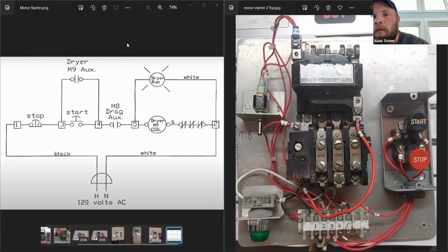I guess from there I'd go with your switch. If your switch isn't pulling in the coil... okay, now the coil is pulling in. The light's coming on as long as you hold the start button down. As soon as you release the start button, they all de-energize.